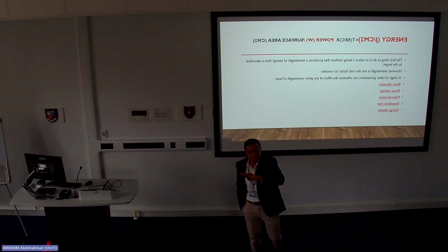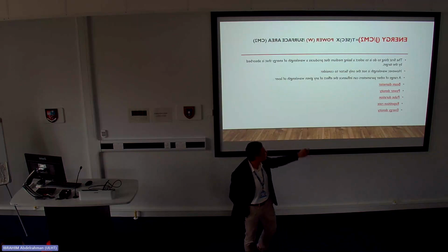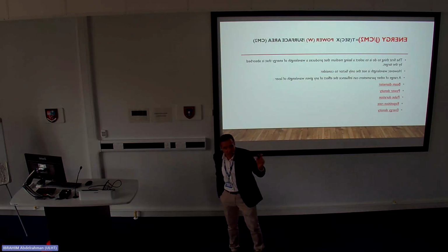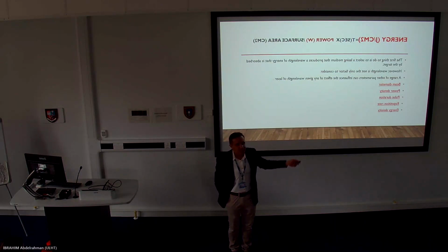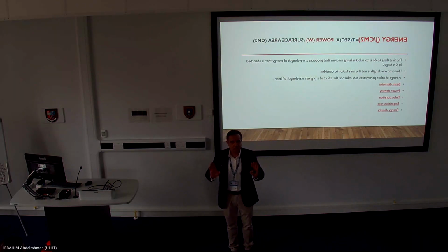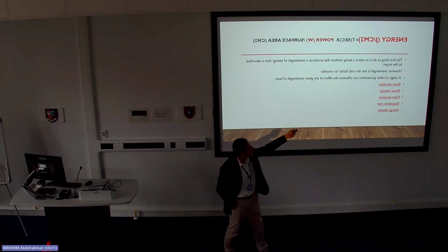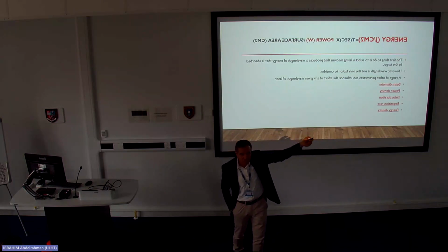Is it continuous? That means there is no repetition, or there is a little bit of repetition. So the time is not only the time of the laser being set on, but also the time of the laser being pulsed in. The device has two parameters for this. The first is the repetition: is it repeated or continuous? And the second is the time that you need to set the laser on. This is directly proportional to your energy, so the more time, the more energy you're going to deliver.